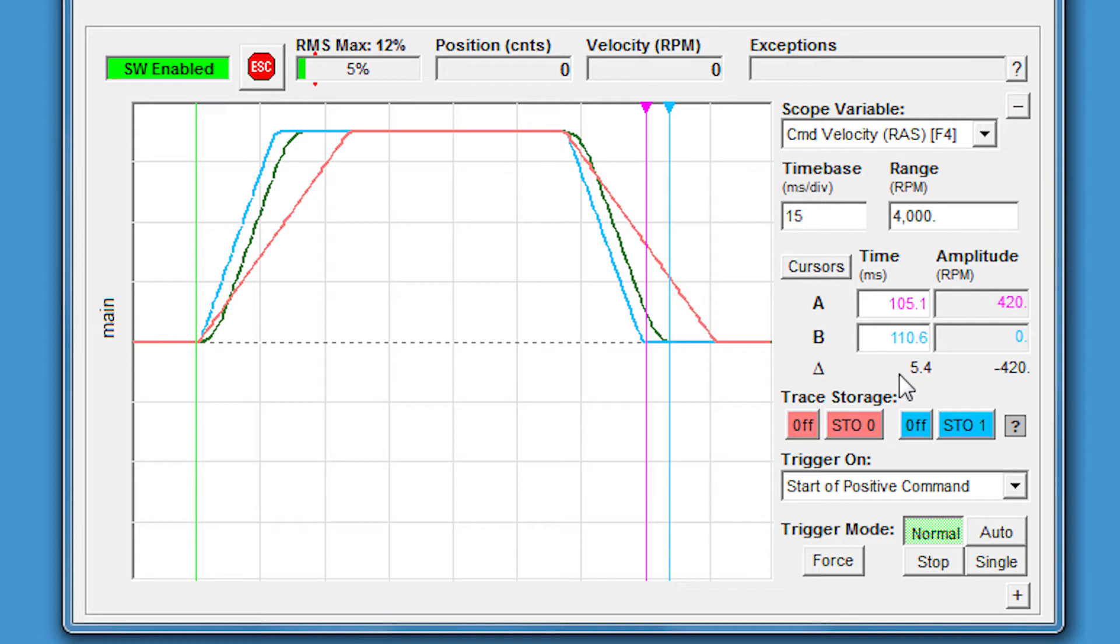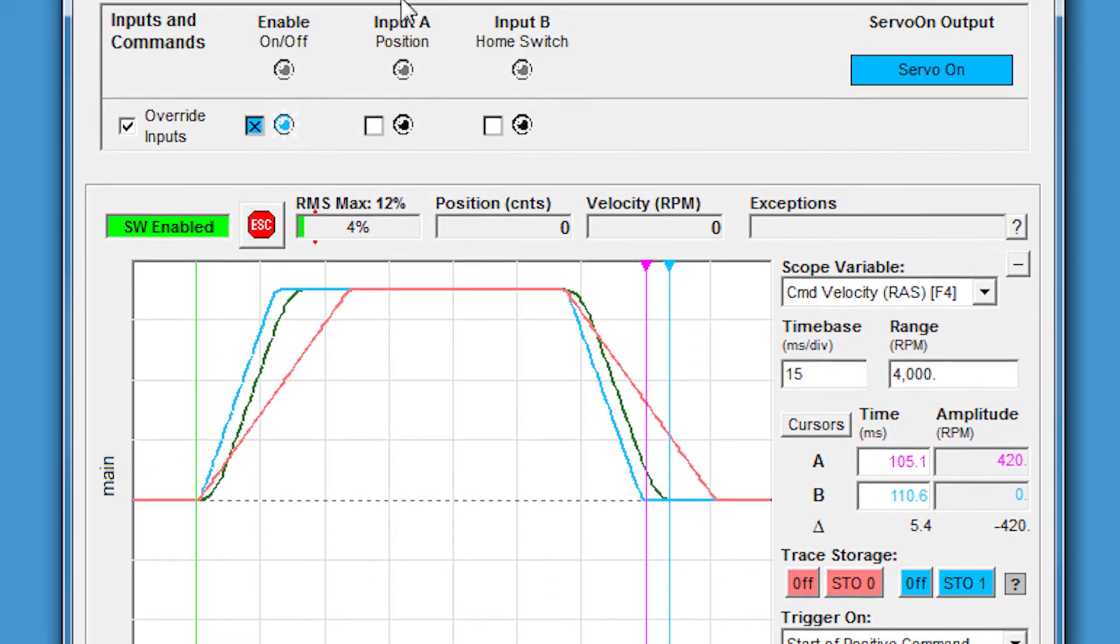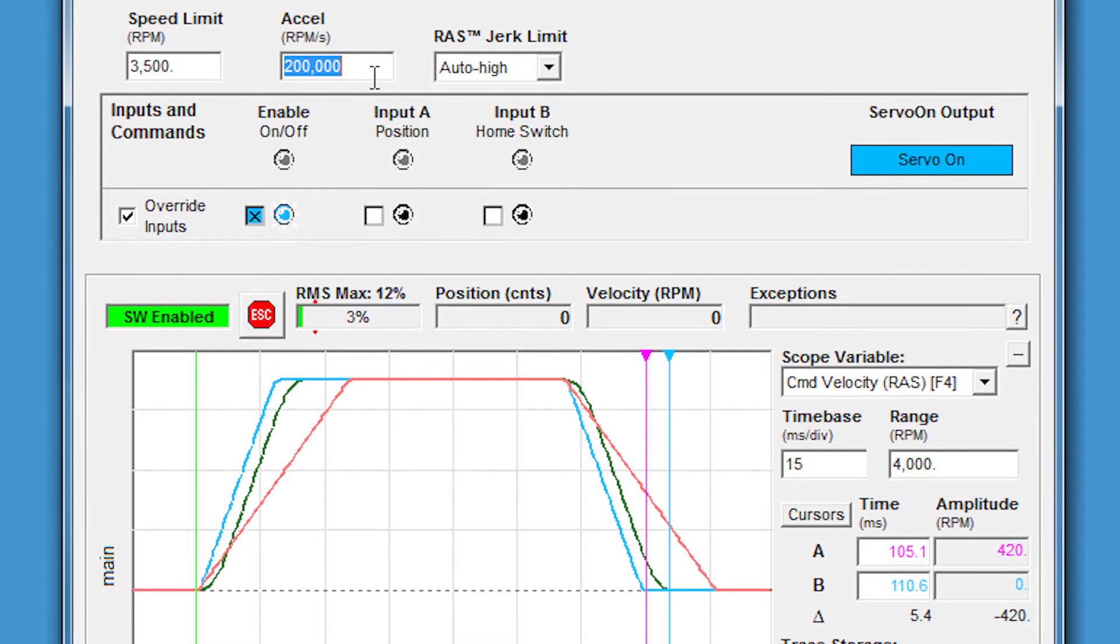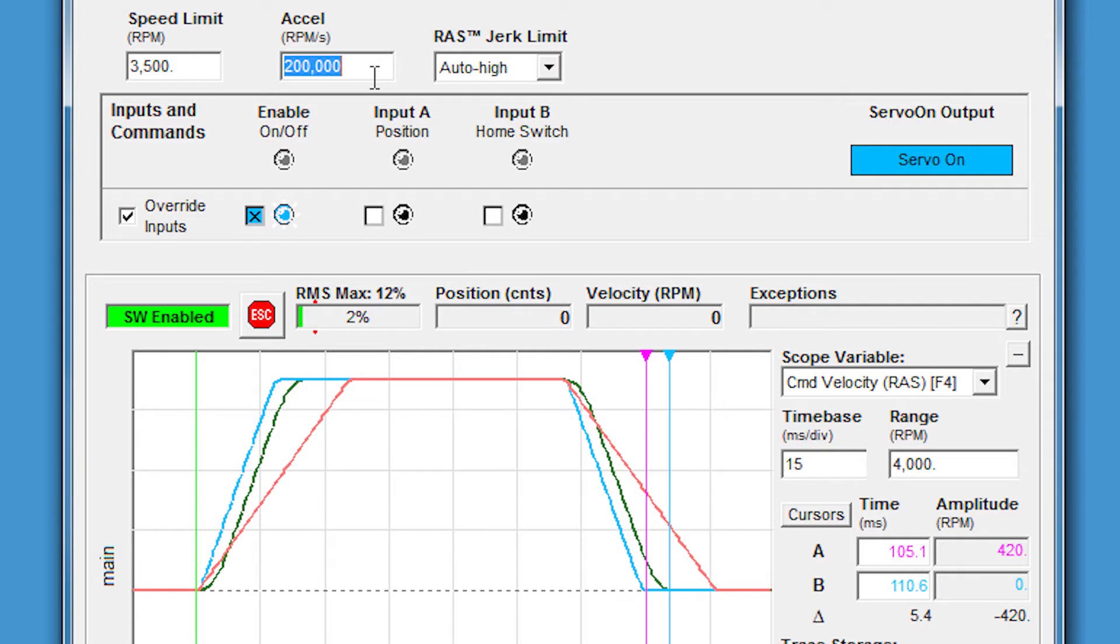But as always, when you're trying to increase throughput, you want to see if you can go even faster to get more parts per hour or decrease another time part in the process. Let's crank this acceleration even higher. There's two things you can do to decrease the move time: either increase the speed limit or increase the acceleration rate. In our application, let's just say 3,500 is the fastest we want to go for our mechanic. So that leaves the acceleration for the only other variable we can play with.